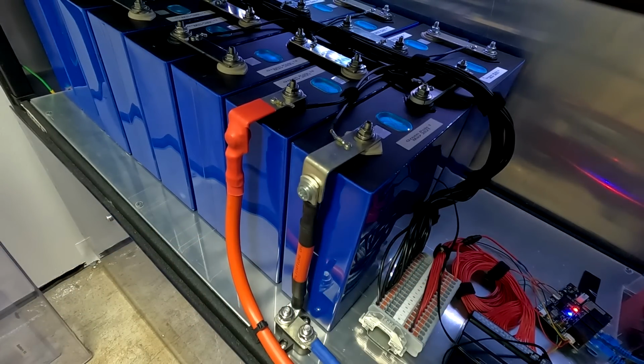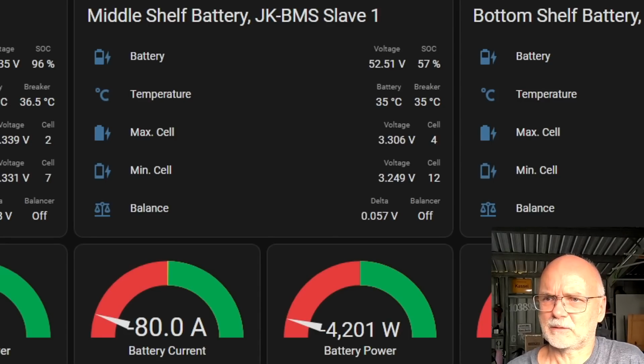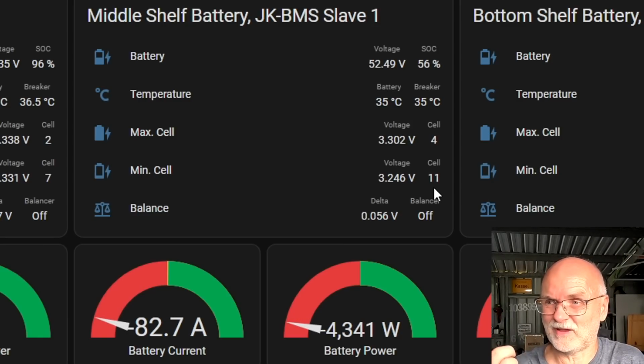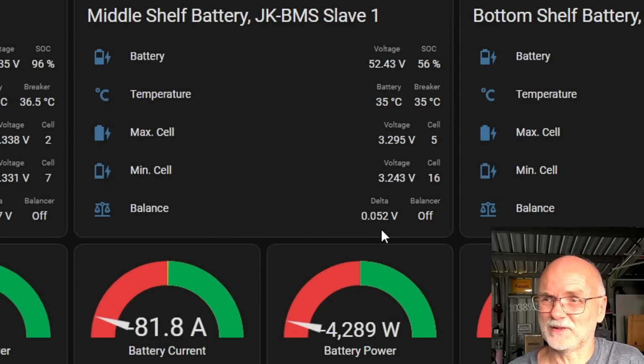Nah, that's not the problem. Okay, we are back on 80 amps here for the middle shelf battery. Deviation 57, it is back on cell number 12 now. This is the one where we've replaced the whole bus bar. Cell number 11, we're still at 56 millivolt deviation. Geez, why is it so difficult to build this battery here?